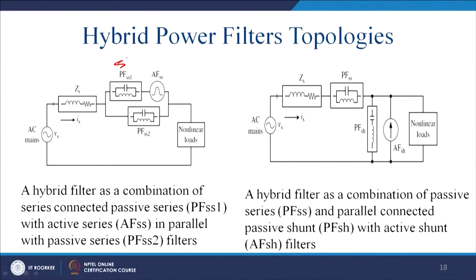We were discussing combinations of active and passive filters. This is also a possible solution, having a series combination in between these passive combinations. Generally it will mitigate the fifth harmonic voltage, and also some portion will mitigate the seventh harmonic voltage. This way it has been met. So it is called the hybrid filter, as a combination of series connected passive filters with active series in parallel with passive series filter.